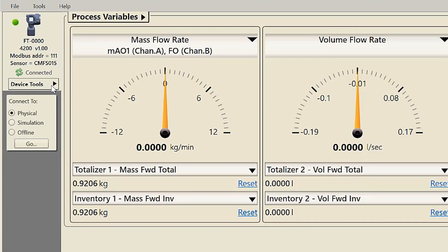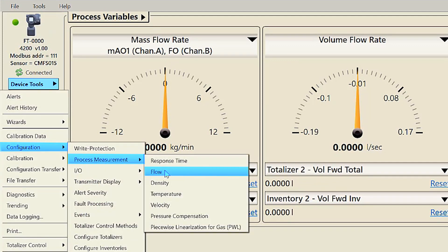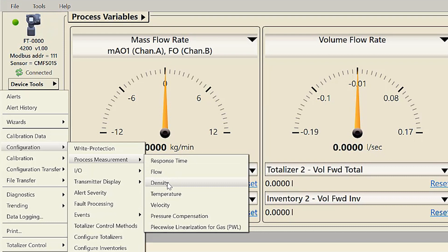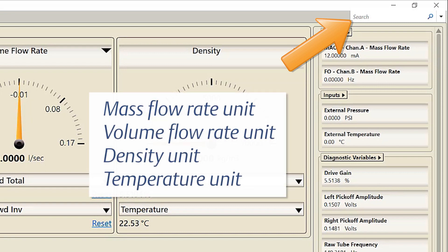Configure the units for mass flow, volume flow, density, and temperature using the following procedures. For configuring mass and volume flow units, use ProLink and select Device Tools > Configuration > Process Measurement > Flow. For configuring density and temperature units, select Device Tools > Configuration > Process Measurement and then select Density or Temperature.